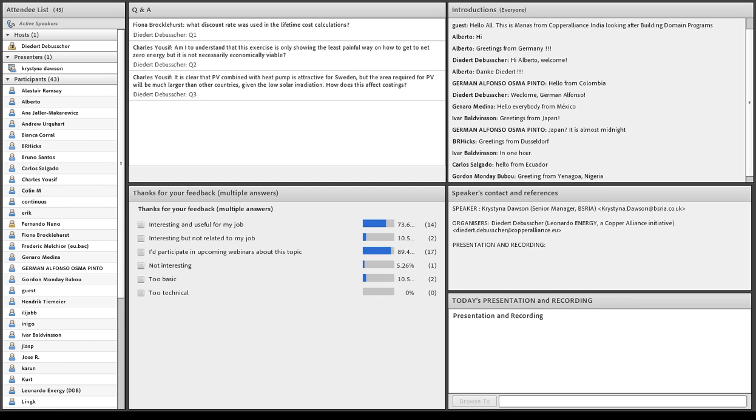It's also, as I have mentioned during the presentation, to note that Sweden has always been promoting ground source heat pumps because of their increased efficiency and longer lifetime. You might remember that air-to-water heat pumps as well as gas condensing boilers have only a lifetime of between 10 to 15 years. In the longer term, the replacement cost has quite a strong impact on the overall lifetime cost of the products. Ground source heat pumps have a much longer lifetime. They can achieve 20 years, which is also making them quite a viable investment from the long-term perspective.